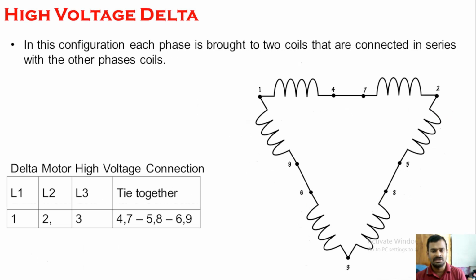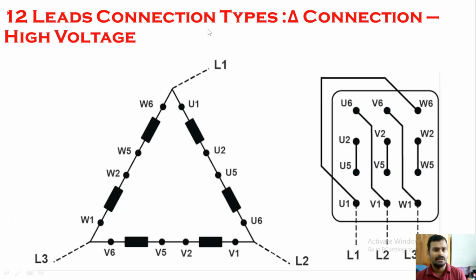And the high voltage delta configuration is very simple. You connect L1 here, L2 at the second terminal, L3 at the third terminal, short 4 and 7, short 5 and 8, short 6 and 9, so that it acts as a high voltage delta configuration.